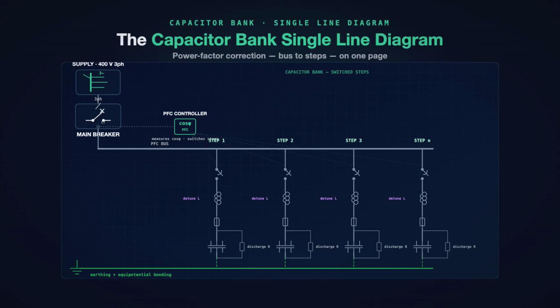This is a capacitor bank single line diagram, a whole power factor correction bank, drawn as one clean line from the incoming bus down to the switch capacitor steps. If you have ever been hit with a low power factor penalty on a utility bill or sized a PFC bank for a plant, this is the drawing at the center of it. One page, the whole bank, the controller, every step, and the protection around each one.